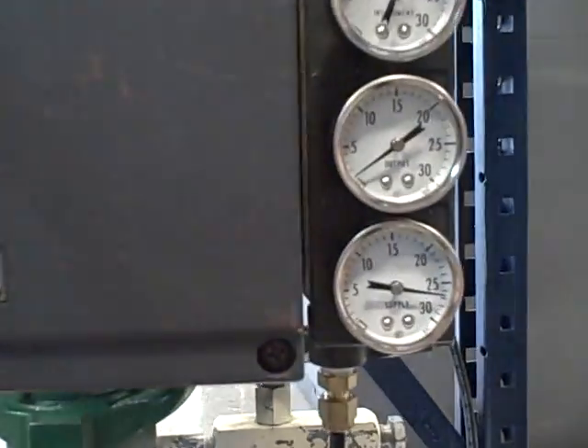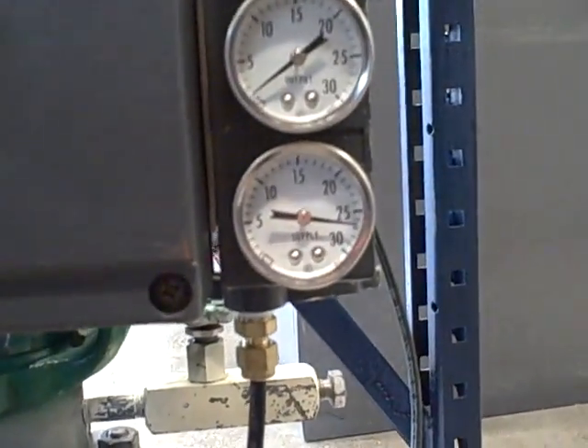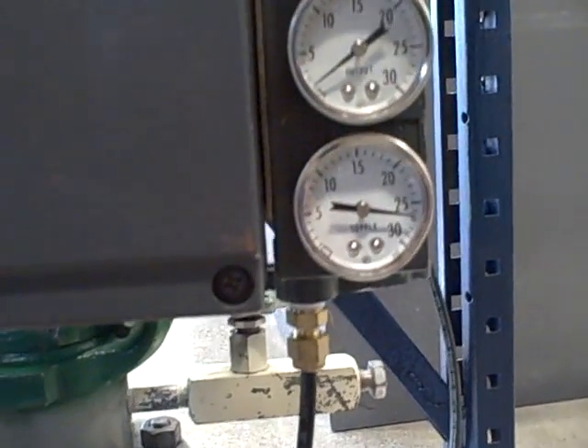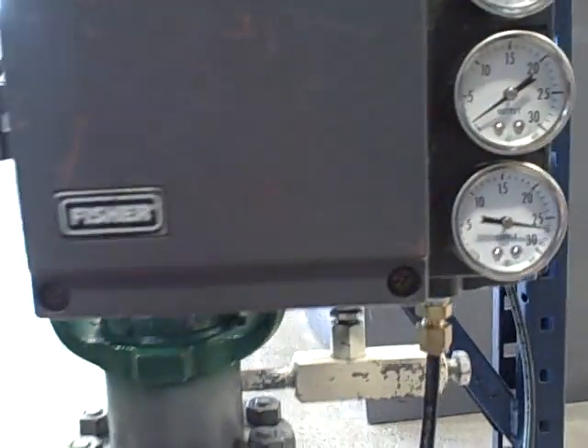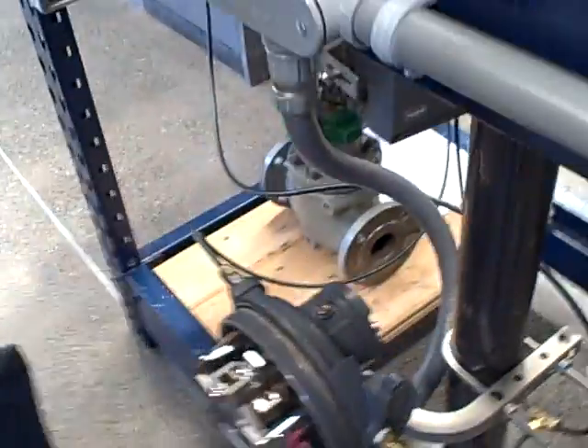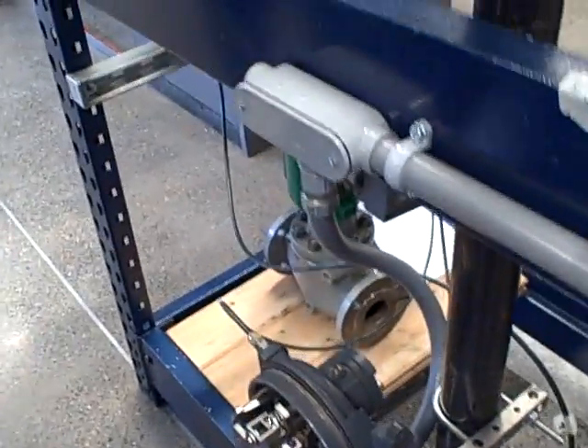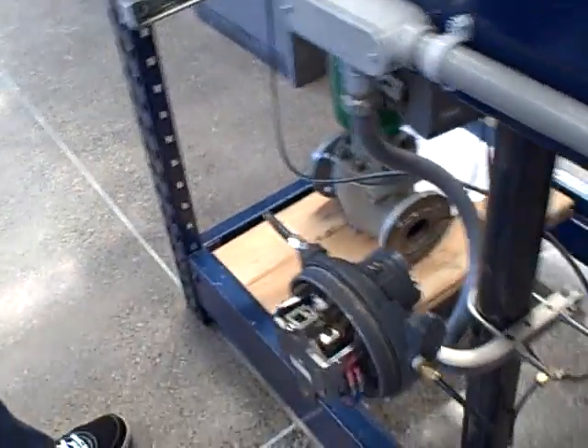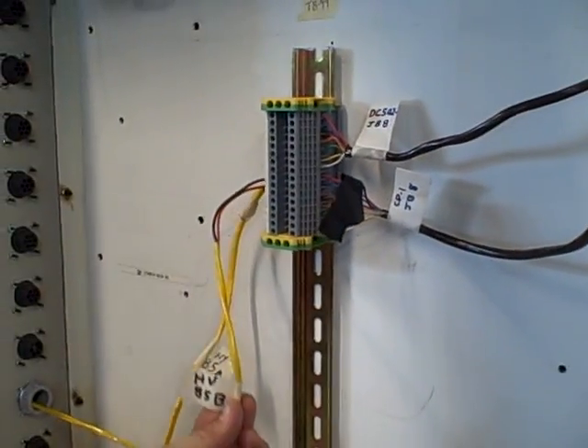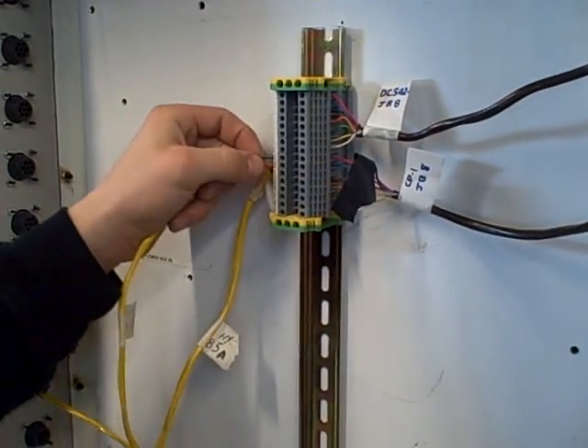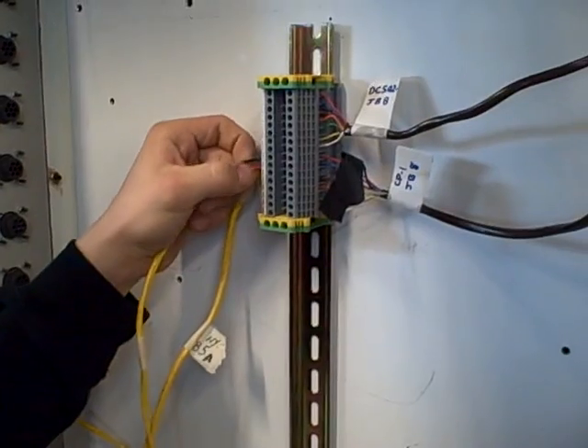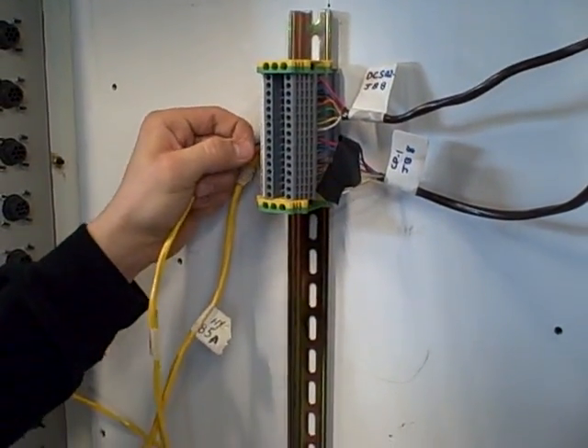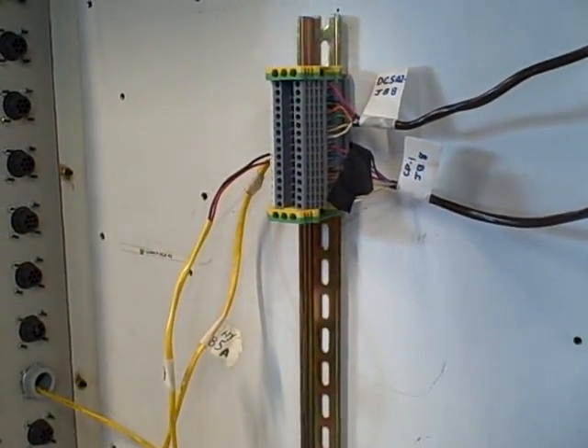Over here, looking at this, you can see this one's cranked up to about 26 or 27 PSI or so. It could probably work fine to 20. But I would definitely note that pressure ranges in the supply required for both of those. Okay. Tugging on the wires over here in JB8. I think we had one more wire to check for more cable. So our HV85B, if we check those, make sure those are securely fastened into the terminal block. Right. And those seem to be good. Good. Okay.